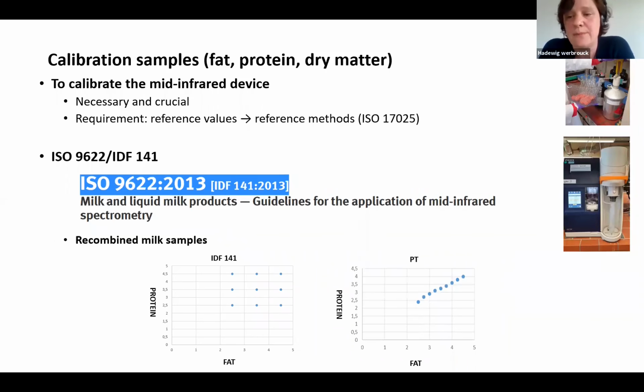Concerning the calibration samples, as already mentioned, with these samples you can calibrate. For FTIR, periodic calibration checks and adjustments with representative milk samples are necessary and crucial, because it determines the quality of the results in routine analysis. The reference value must be determined by using the reference methods. This is important. The composition of milk shows a high variability, which makes it more complicated than chemical analysis of pure molecules, where they work with a dilution of a pure molecule.